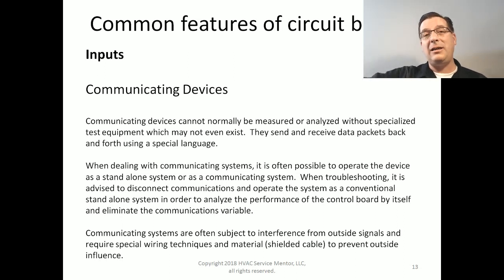So if we take the communicating aspect away and we operate it as standalone non-communicating equipment by connecting it to a conventional thermostat, and if it works correctly, now we can start to narrow down if it's a communication issue or not. Is it the user interface on the wall, or is it the board in the furnace, or what the heck is it? So being able to switch it from communicating to non-communicating is a big help in moving to diagnostics.